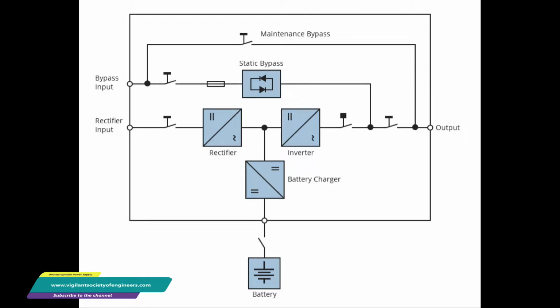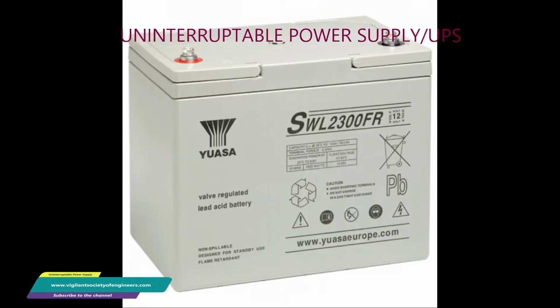The charger of the UPS is separate, and it is designed to provide charging to the battery unit. This is common on large UPS systems and less common on small sub 3 kVA units. The battery provides storage. So it's a storage device, and mostly they are VRLA batteries.